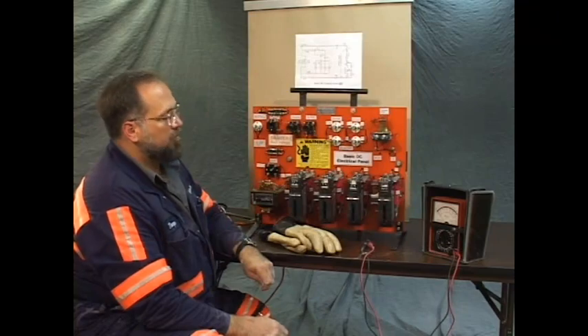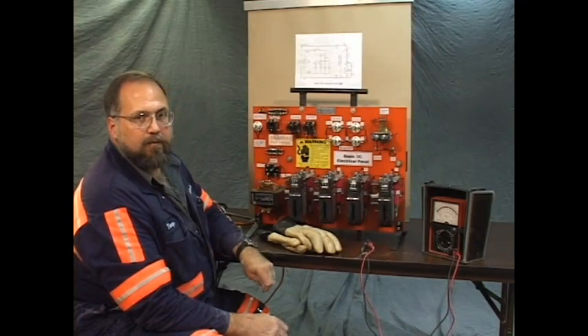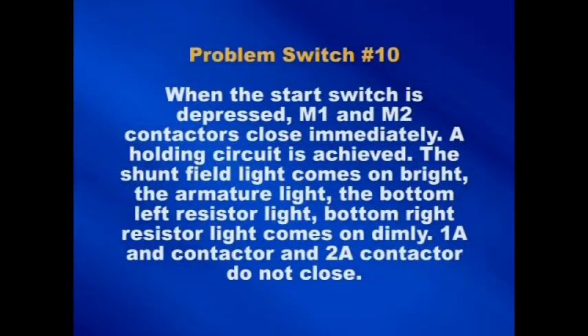F2 lead open. That's that. If the apprentice electrician should draw problem number 10 at the testing center, this is what he would hear. When the start switch is depressed, M1 and M2 contactors close immediately. A holding circuit is achieved. The shunt field light comes on bright, the armature light, the bottom left resistor light, the bottom right resistor light comes on dimly. 1A contactor and 2A contactor do not close.